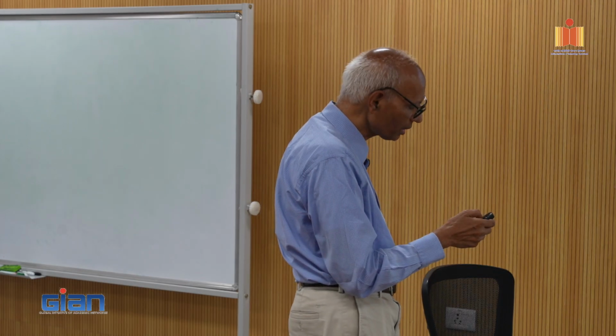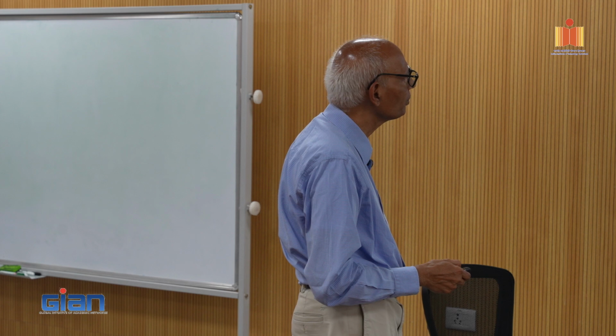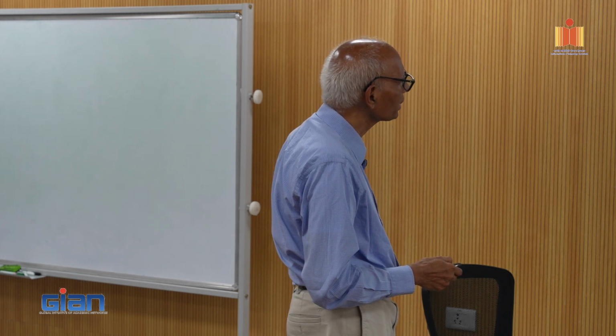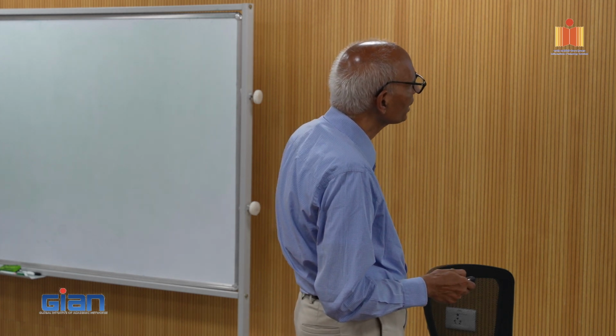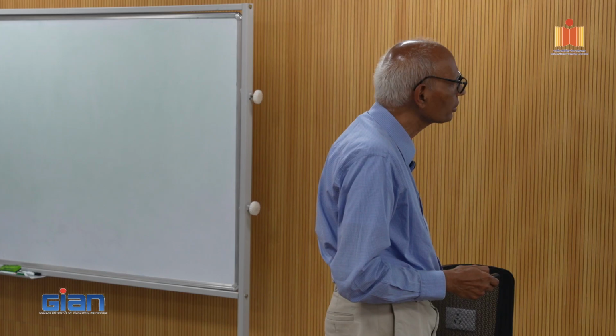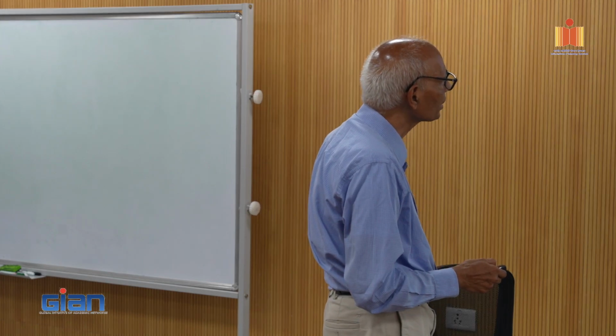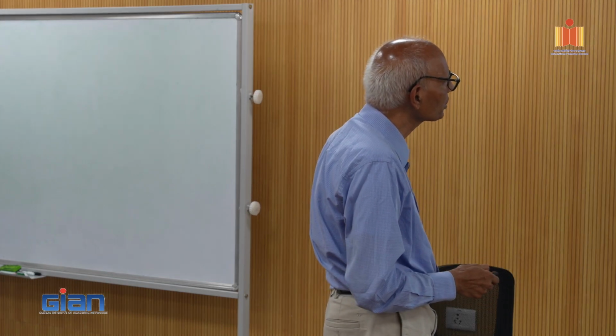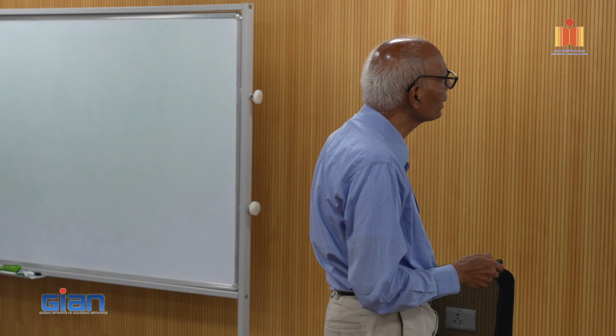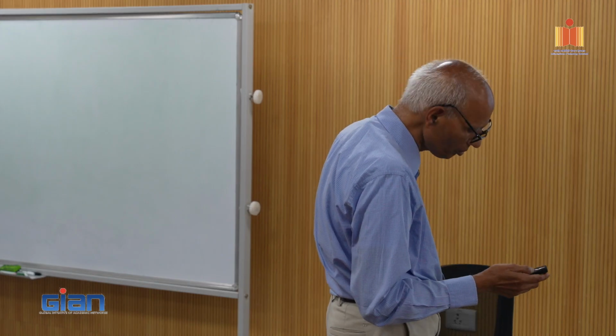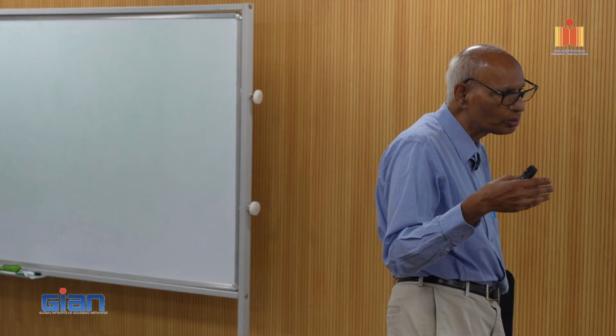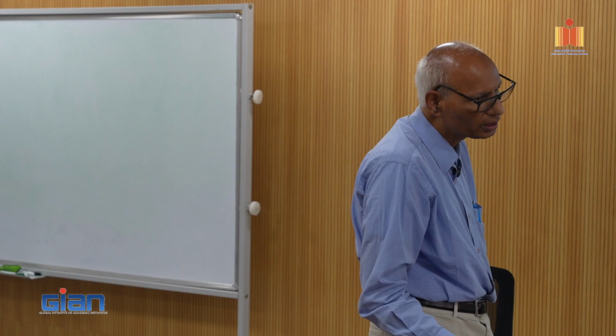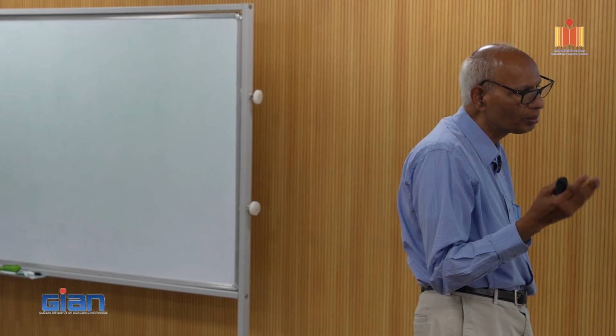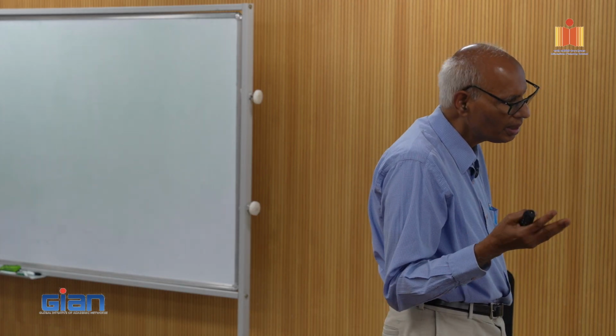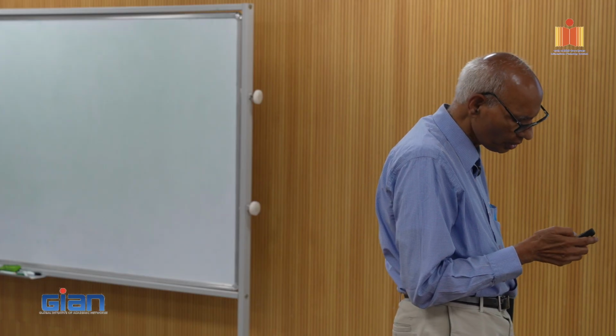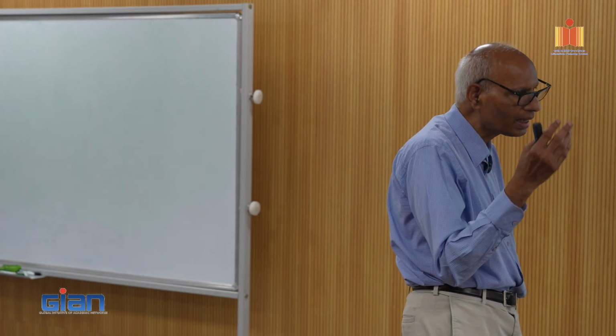It is very similar to the TG51 calibration from AAPM, and ICRU, another agency which makes recommendations on how to use protons, has adapted 398 with some small changes. This TRS 398 has recently gone through some revisions because of those people who want to reduce the uncertainties in the dose calibration. So they have come up with some new factors which change the dose probably by less than 0.5% or something. But if everybody adapts, that's good.